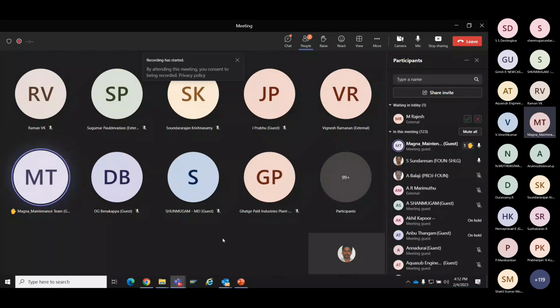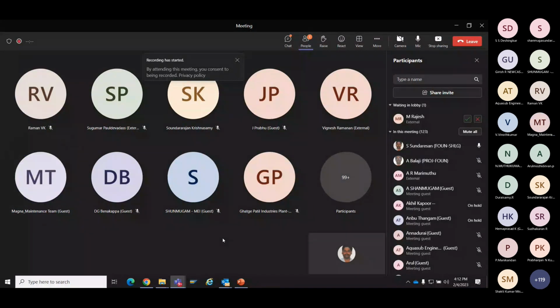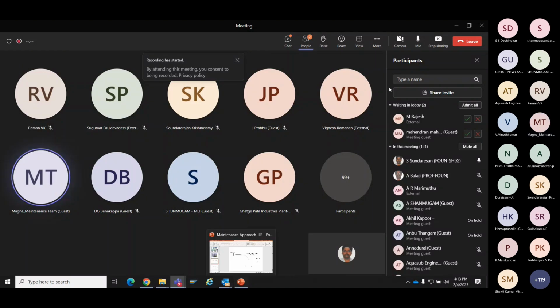That offline thermography, how do you measure it, with an instrument or physical measurement at that point? There are two things I explained, the HT line, that is a thermal imaging camera. How do you position it? Everyone is now familiar with using their own cell phone camera, correct? Even a schoolboy uses a cell phone camera to take selfies and other pictures. It's very similar to that. You have a thermal imaging camera, and you just position it at the point where you want to do the thermal analysis. When I go to the slide you'll be able to see the difference in temperature, let me go back to the slide for this.